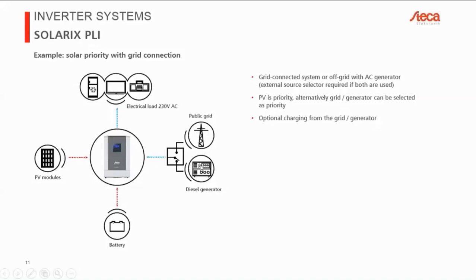If you're using both a public grid and a diesel generator, you will need to have an external switch. It can be an automatic switch, but it must be externally controlled. The PLI cannot control it. The PLI can only deal with one AC input. But if you have a priority selector outside of the SOLARIX PLI, you can deal with two AC inputs by simply choosing one or the other at any point in time.